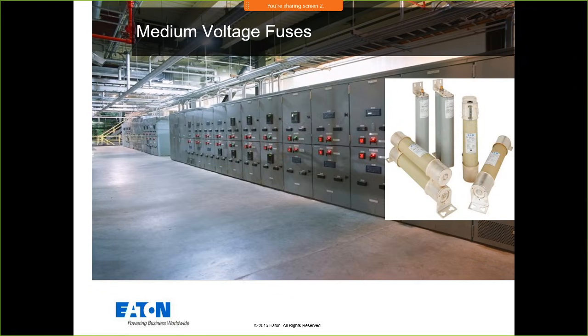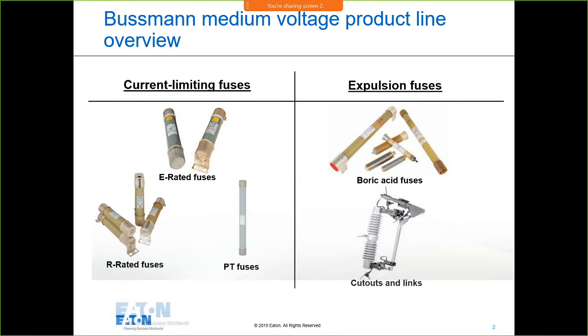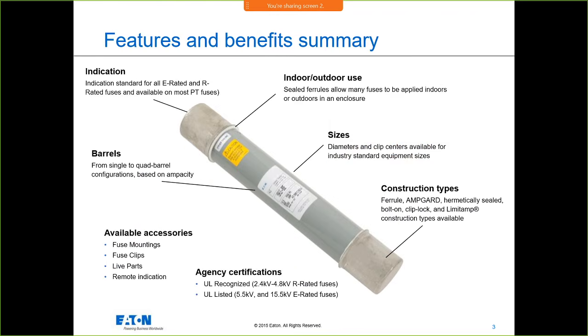All right, medium voltage fuses. We have current limiting and your E-rated, your R-rated, your PT fuses, and we have expulsion type fuses, boric acid type, and your cutouts. These are what you'll see. Some of these you'll see up on the utility poles, and some of these you will see in your medium voltage equipment. The construction of the fuse is very similar to your low voltage fuses.